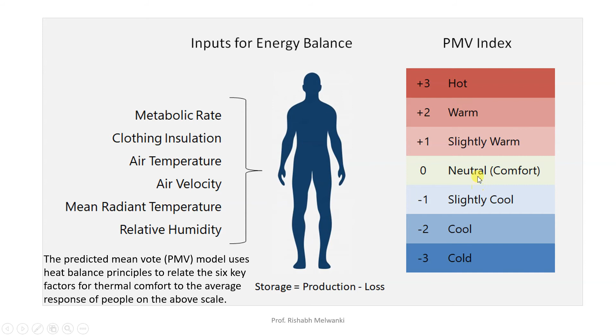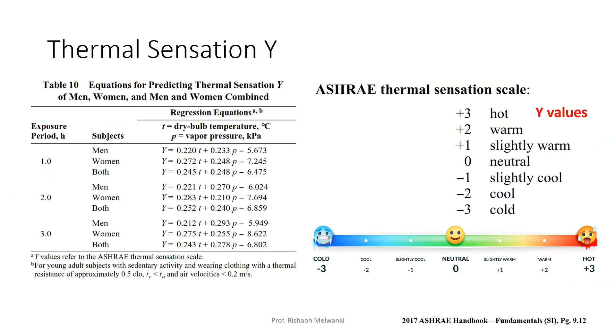Now here you can see a diagram of PMV, predicted mean vote, versus PPD, predicted percentage of dissatisfied. This is the sensation scale on the x-axis. At 0, the thermal environment will be neutral. If you go towards the right, it will be too hot, and the left will be too cold. To decide the acceptable thermal environment for general comfort, PPD, the percentage of people dissatisfied, should be less than 10%, and the PMV range is from minus 0.5 to plus 0.5. Based on this, the comfort chart is made. Now we will go to the graphical method of the comfort chart.